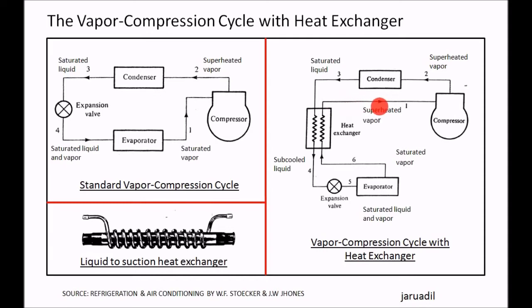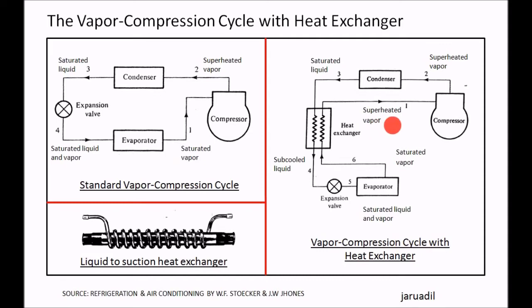And the saturated vapor will slightly increase in temperature. It will become superheated vapor before entering the compressor. Unlike in the original cycle, where the refrigerant entering the compressor is just saturated vapor. Here, it is slightly superheated — just a few degrees, around 10 degrees of superheat.